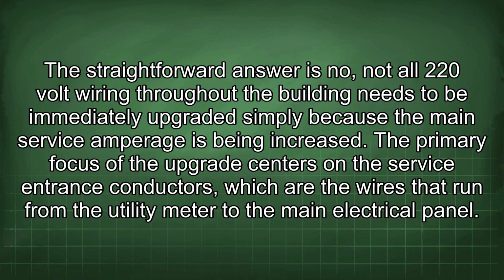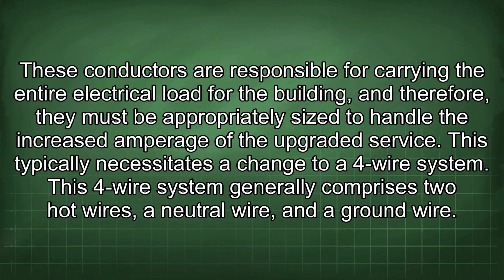being increased. The primary focus of the upgrade centers on the service entrance conductors, which are the wires that run from the utility meter to the main electrical panel. These conductors are responsible for carrying the entire electrical load for the building, and therefore, they must be appropriately sized to handle the increased amperage of the upgraded service. This typically necessitates a change to a 4-wire system.